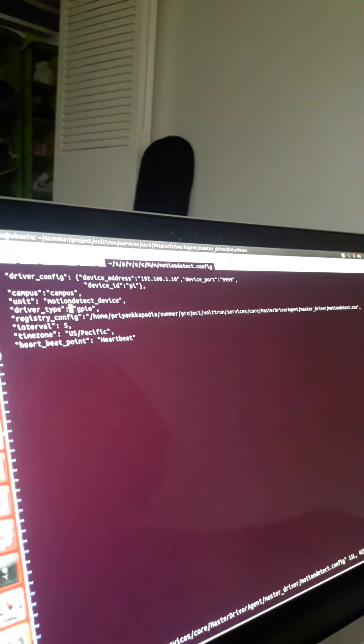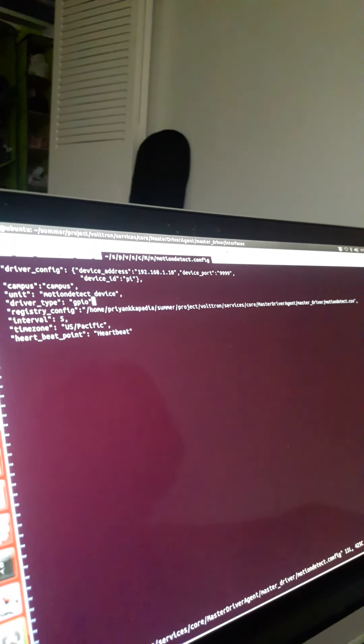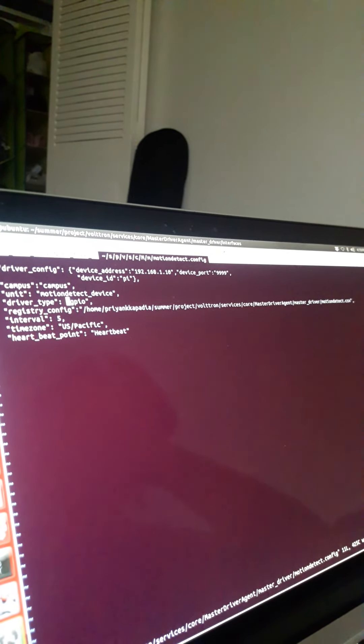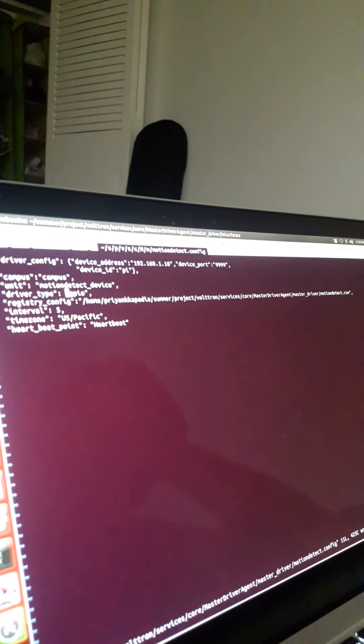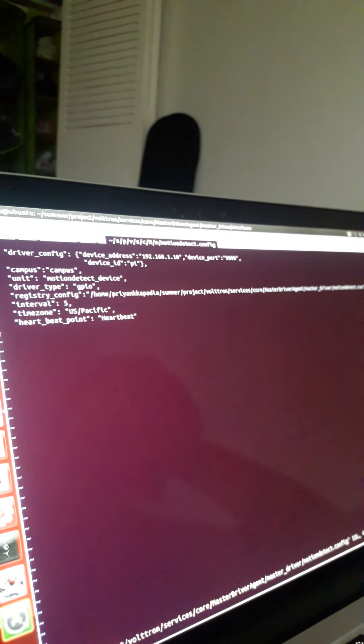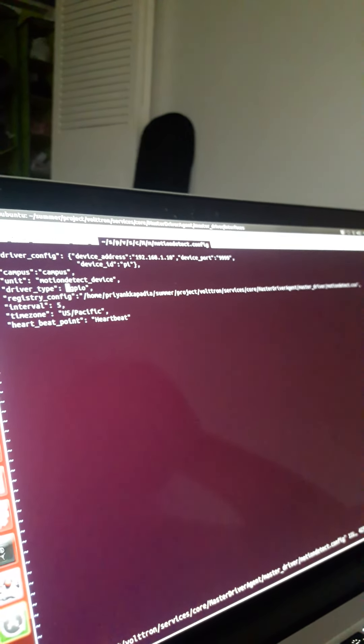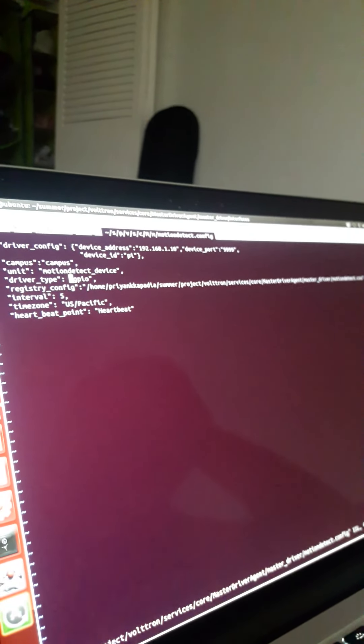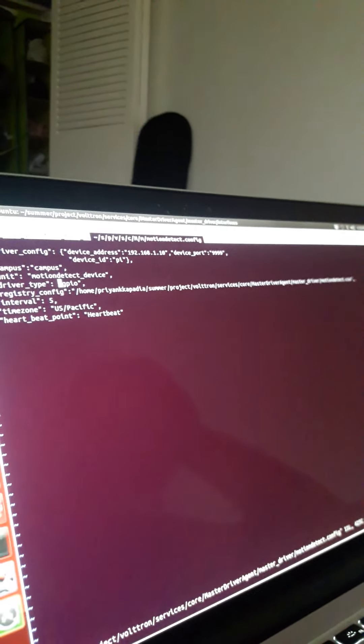The driver type is an important property because it decides which interface it should go into. If you have driver type as modbus, the master driver will go to the modbus interface. If it is GPIO it'll go to the GPIO interface, and if it's BACnet it'll go to the BACnet interface.